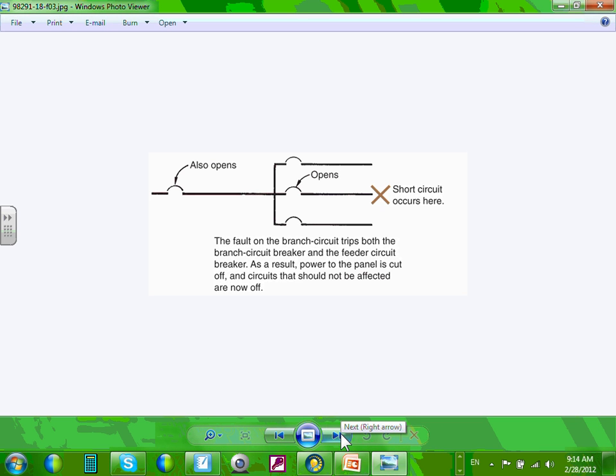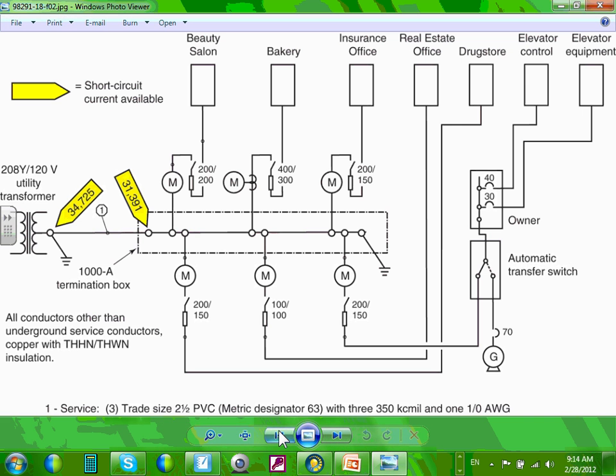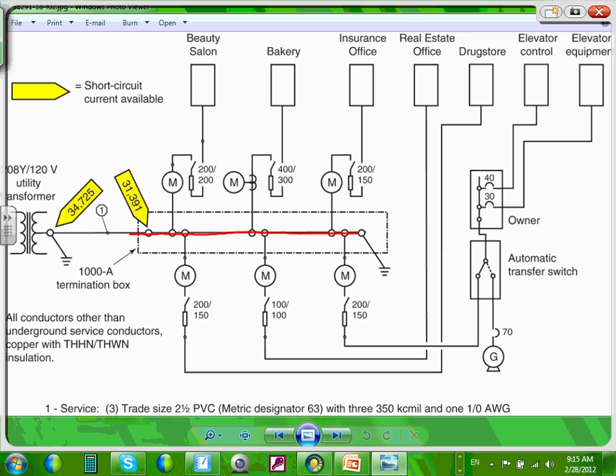I'm sorry, Rob, do you have any question? More of a light question. I was looking at that last picture and interpreted that as a bus bar. Yeah, this one here is actually a terminal box. They brought the feeder here and tapped the feeder. Can you see how they're bringing it here? It's the same principle as a bus bar. The bus bar is manufactured, it has a terminal in it, and you're just tapping into it. Imagine a gutter with lugs inside it. But if your distance to the gutter becomes a length, do you calculate that? Yes, because every time you have length, you have impedance.